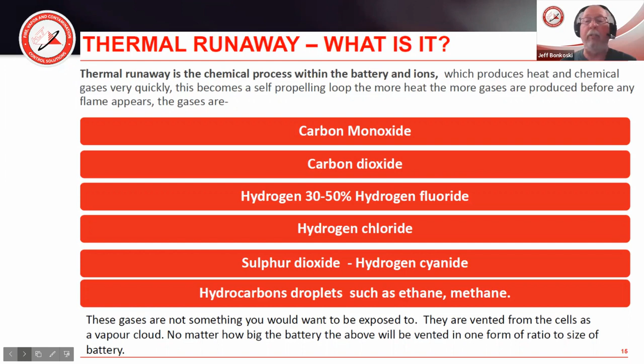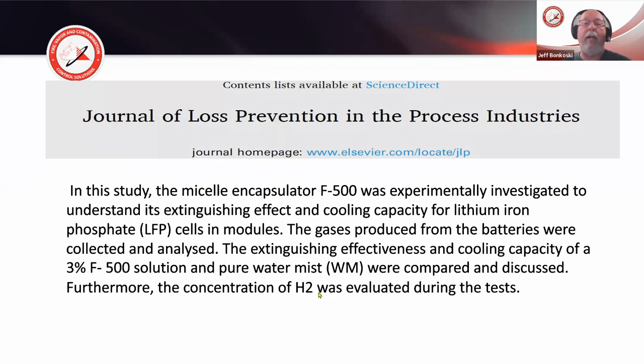This leads us to a study we recently found that came from China. I'll give Hernan credit, he found it through a Google search. It looked at the spherical micelle encapsulator agent and investigated its cooling capacity when it came to lithium phosphate cells. It also looked at the gases produced when the batteries burn, collecting and analyzing them, and the cooling capacity of the 3% solution. They compared it with water mist, since water mist is a trend people think is very effective, and they also evaluated the amount of hydrogen released during these tests.